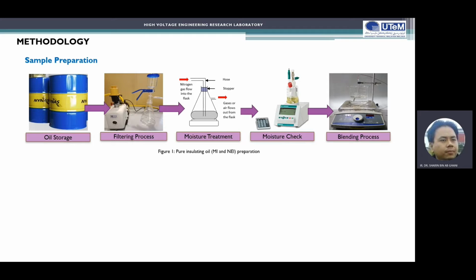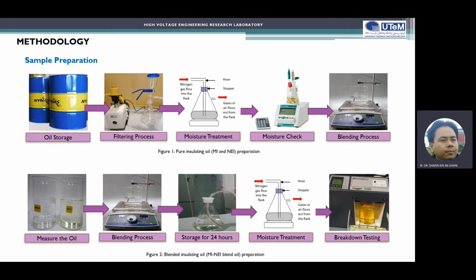So this is our method. First, in the preparation: oil storage, the filtering process, moisture treatment, moisture check, and then the blending process. For the blended insulating oil, we first focus on measuring the oil percentage for the blending process. We focus on the storage itself, because we want to control the effect of moisture, and then do moisture treatment, and also the breakdown testing.